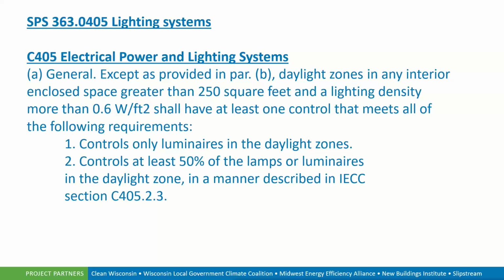405 pertains to electrical power and lighting. We also offer a session on exterior or commercial lighting systems and power allowances and power factors determination. And this is as the amended code is written. Any enclosed space greater than 250 square feet with a lighting density of more than 0.6 watts per square foot should have at least one control that meets all of the following: able to control luminaires in daylight zones, and controls at least 50% of those lamps or luminaires in a daylight zone. And that falls in conjunction with C405.2.3, which would be under the daylight zoning requirements.